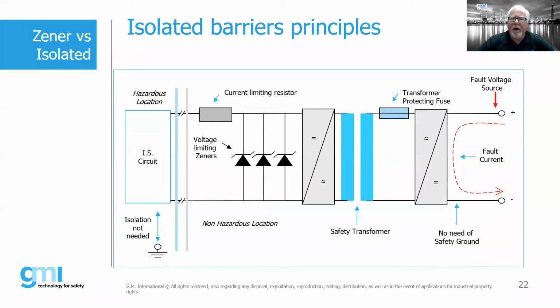So now an isolated barrier. Notice that we still have our fuse, we still have our current limiting resistor, we still have Zener diodes, but in this case, we actually have incorporated a safety transformer. So under this scenario, we have a fault condition coming in from, say, our control panel, but because it's isolated by the use of a safety transformer, that fault will not transmit over into the hazardous location on the left-hand side. So notice here, there is no need for a safety ground.